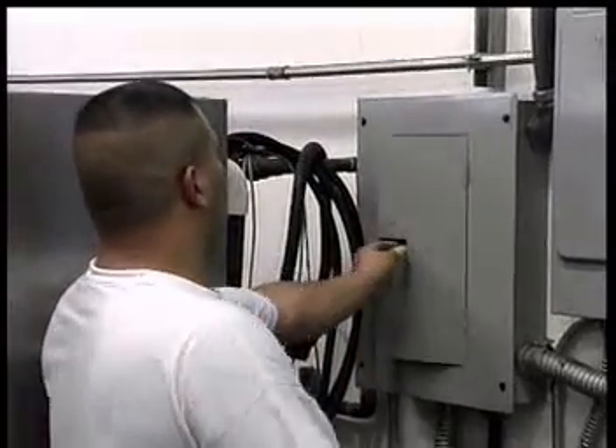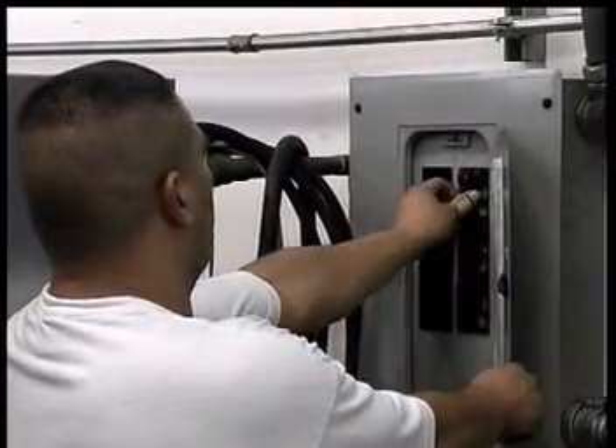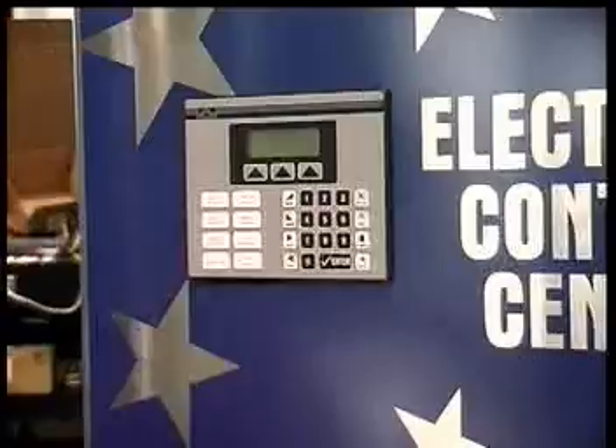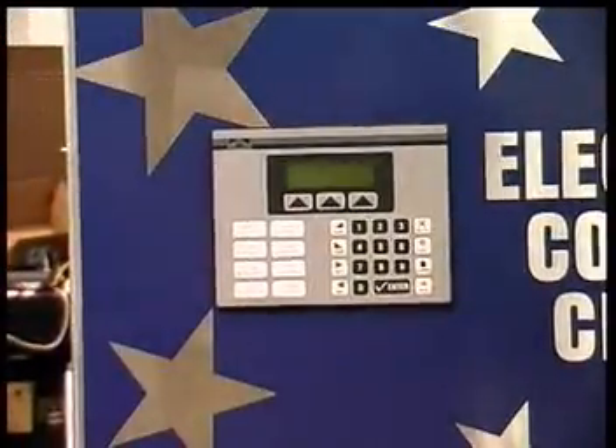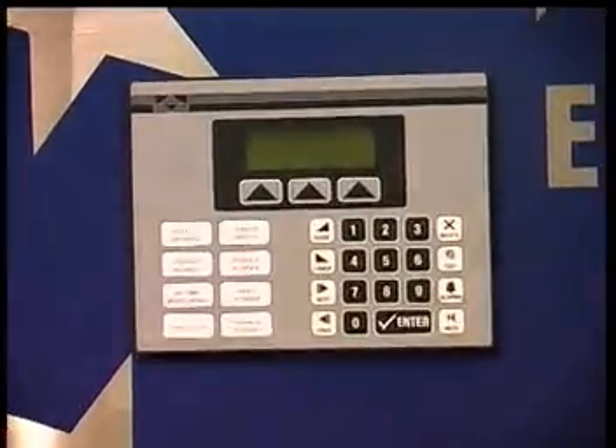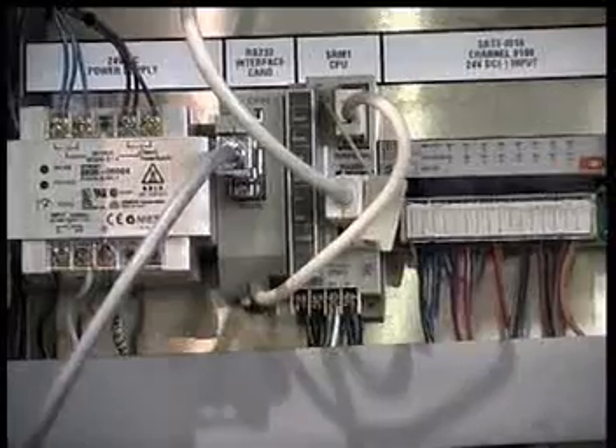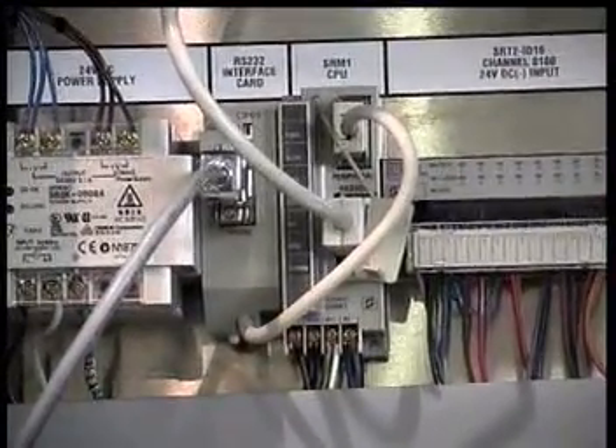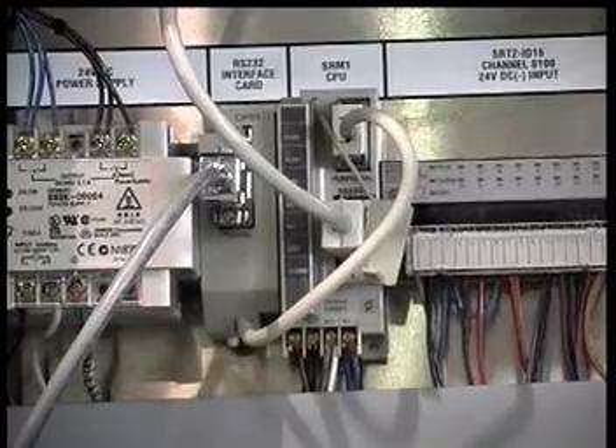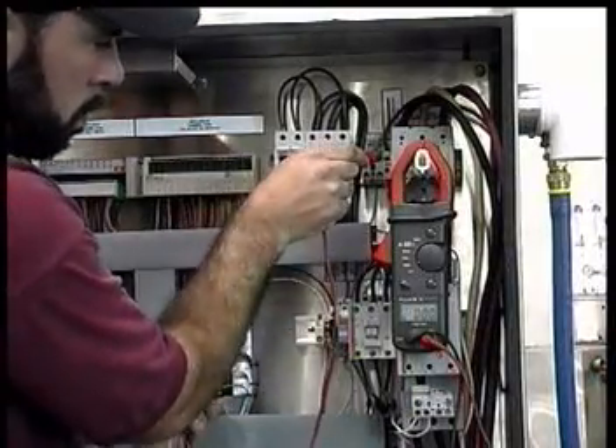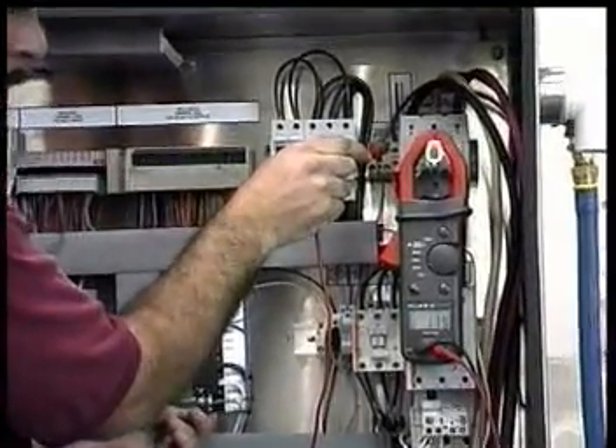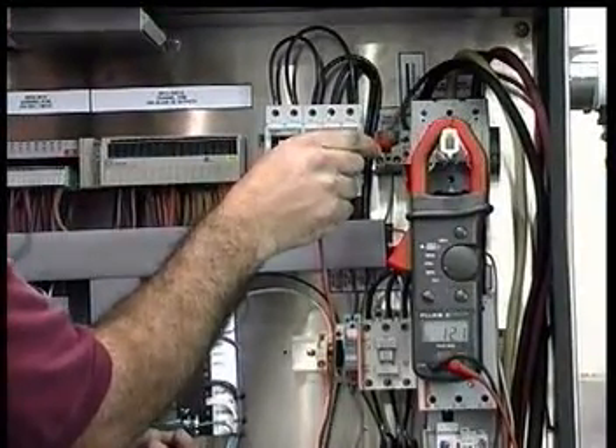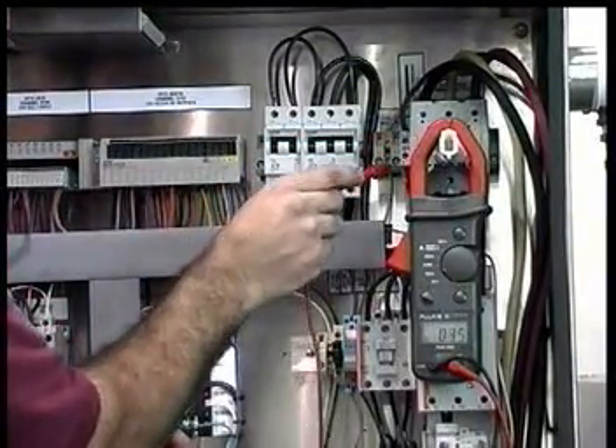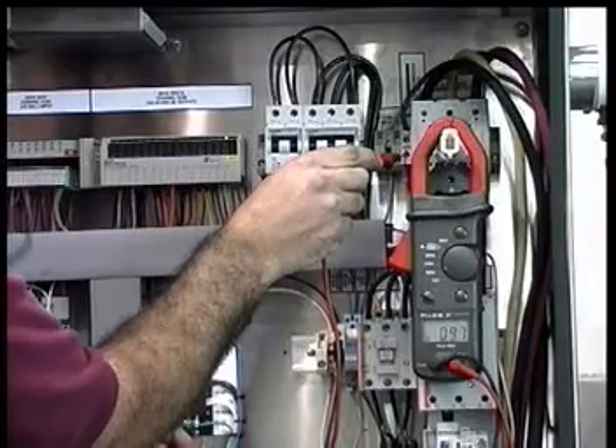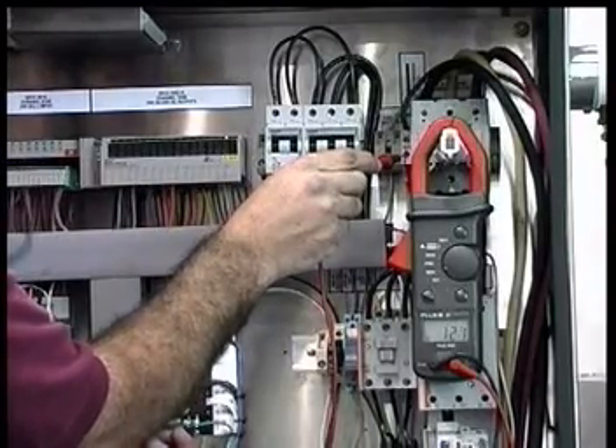Make sure incoming power to the building is on and the designated breaker is not tripped. Symptoms indicating problems with the 110 voltage would be no display on the interface panel and no power lights on processor or input-output cards. Check the incoming power from terminal 37 on the auxiliary switch in the control panel to ground. Then check from terminal 38 and ground. There should be 110 volts present on both locations.